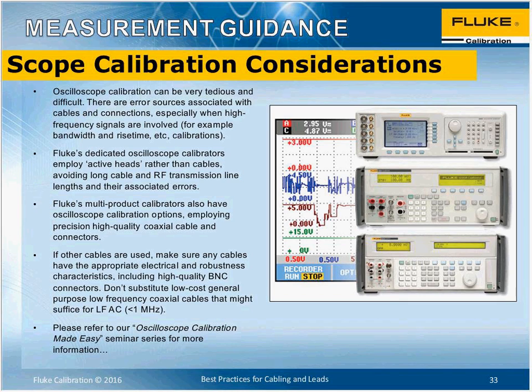So cable connections are okay, but we do recommend and provide really good, high quality precision coax cables, as Rich mentioned right up front, and good quality connectors. Even though BNC is not usually recognized as a metrology grade RF connector, many oscilloscopes use them right up to the gigahertz or so. So we have to be very careful and provide good quality BNC connectors for use with our scope cal options. So if you're going to substitute any other cables for oscilloscope calibration, be very careful, and I would recommend that you don't, unless you procure some really good precision, much more expensive cables to do that with.